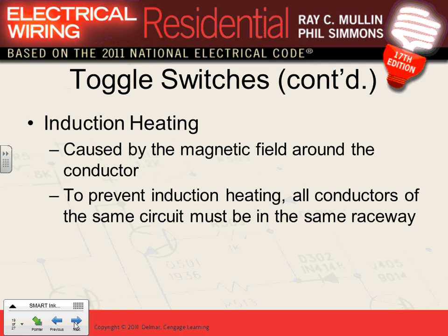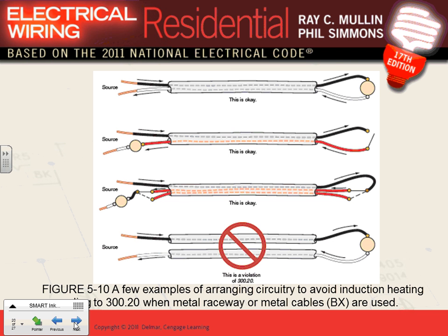It screws up. You have a lot of cables, 14.2 and 14.3, that you're going to be throwing around. Keep in mind always, the conductors of that particular circuit have to be grouped together. So if I have 2 branch circuits, the conductors of branch circuit 1 and branch circuit 2 don't have to be in the same cable or conduit. Okay? Why do they do that? Inductive heat.